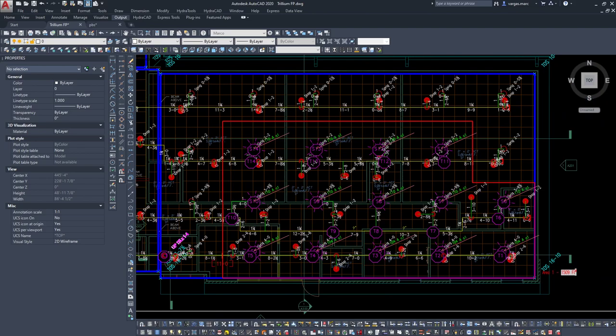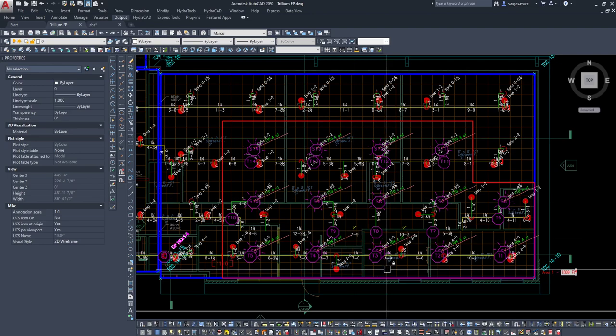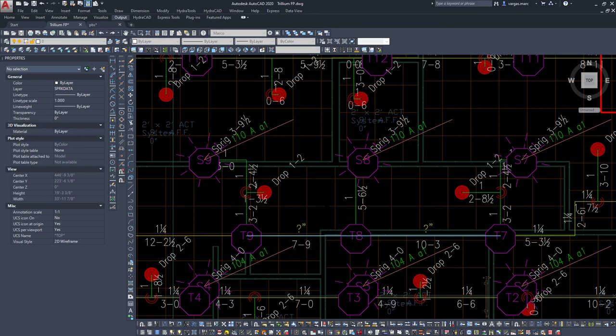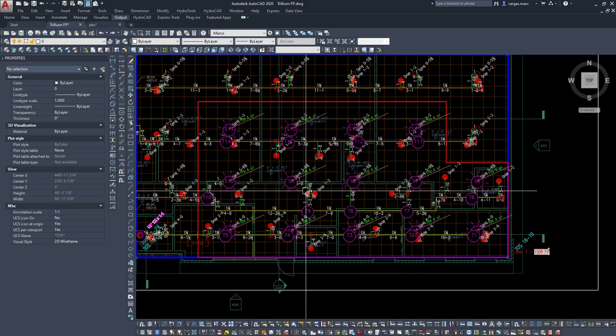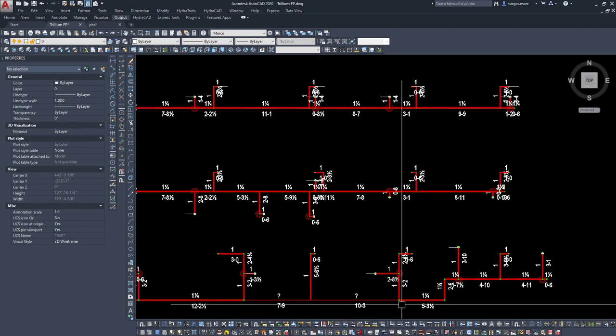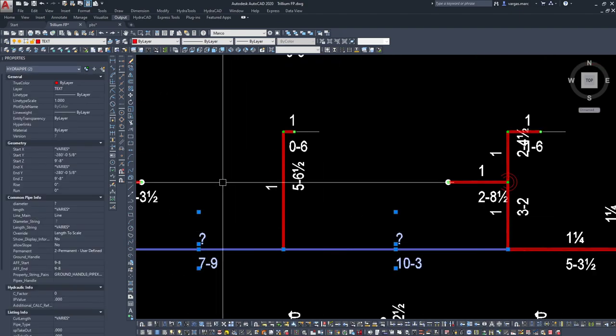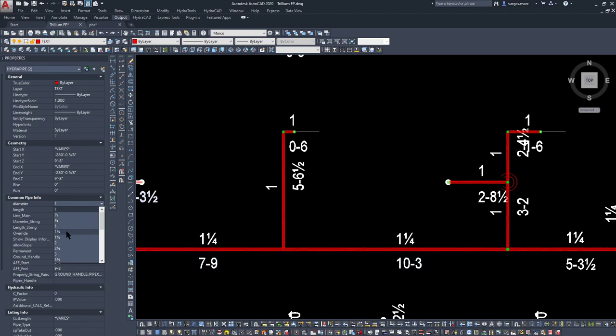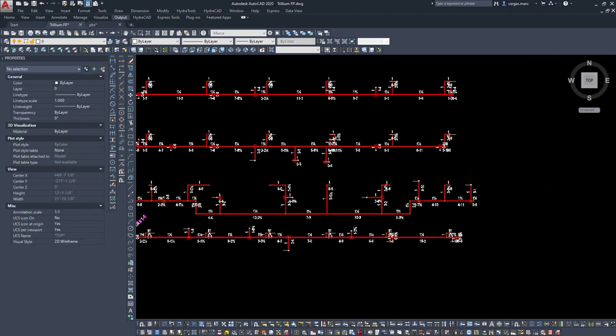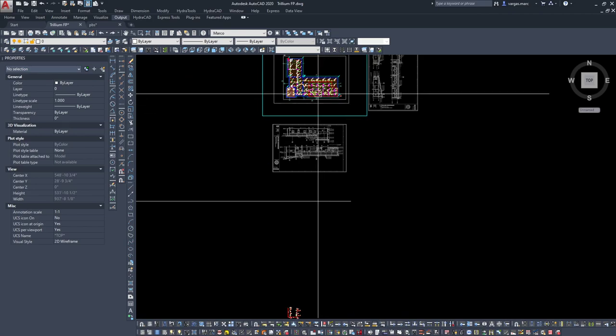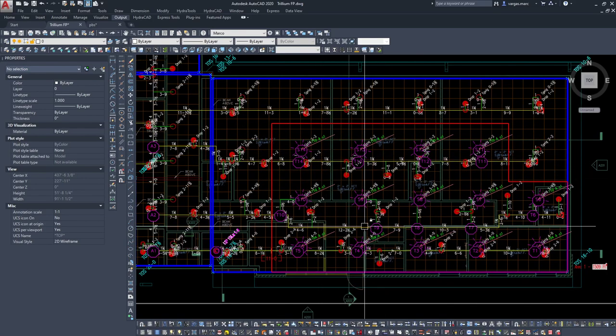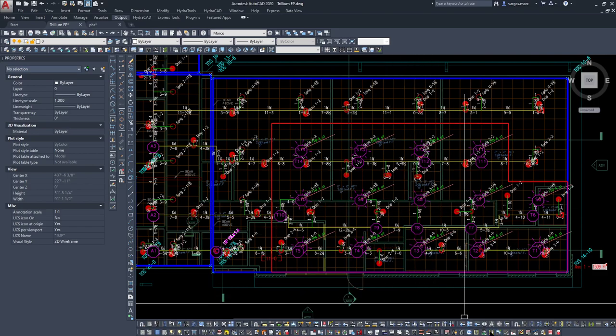Looks like we got some missing pipe sizes there, so let's get these fixed. I know they're going to be messed up in the model, but one quick way to fix them is using properties — select them and under diameter it's inch and a quarter. I should have seen that and looked for it; I just assumed I did everything correctly, but it happens — you just fix it and move on. All the nodes are in there, that's fixed.